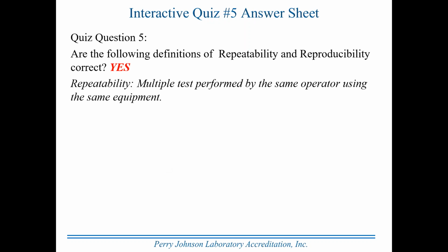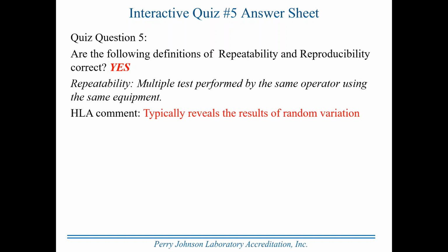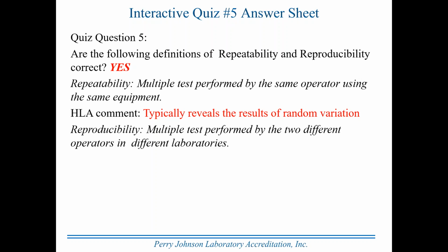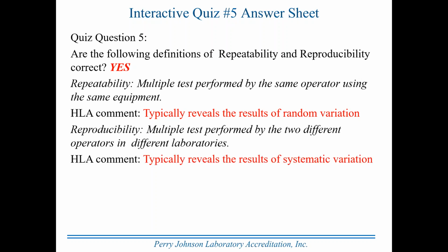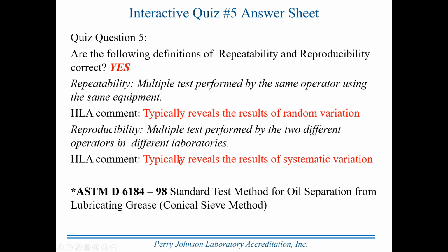Repeatability, multiple tests performed by same operator using the same equipment. Typically, this reveals the results of random variation. Reproducibility, multiple tests performed by 2 different operators in different laboratories. Typically reveals the results of systematic variation. And again, these definitions were found in this specific ASTM D6184-98 test method. It's found on page 3 of 4 of that standard.